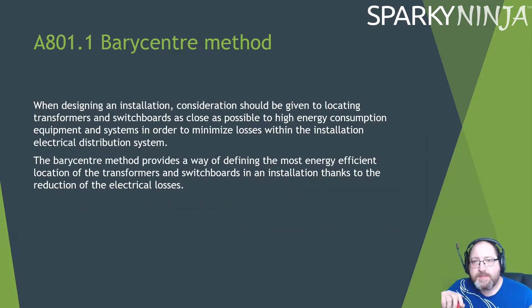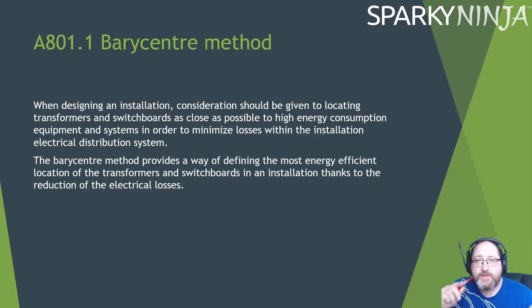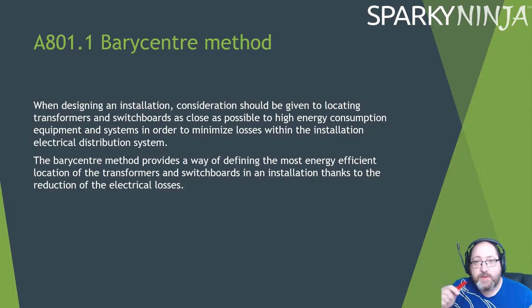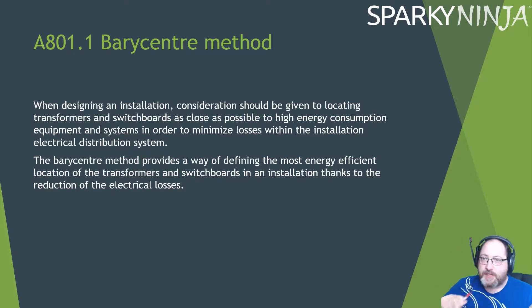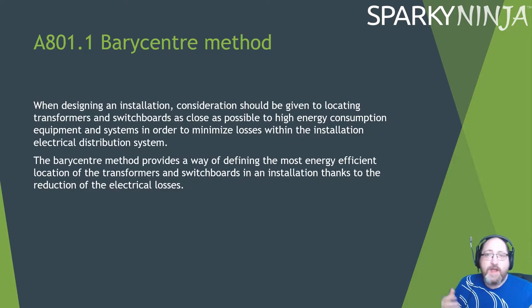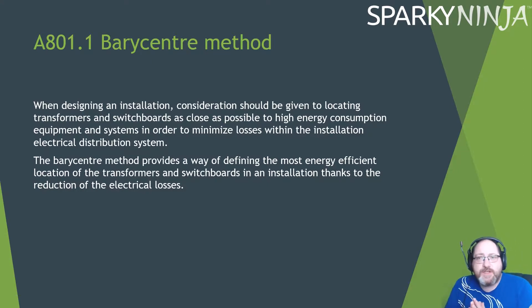The barycentre method: when designing an installation, consideration should be given to locating transformers and switchboards as close as possible to high energy consumption equipment and systems, in order to minimize losses within the installation electrical distribution system. The barycentre method provides a way of defining the most energy efficient location of transformers and switchboards in an installation.